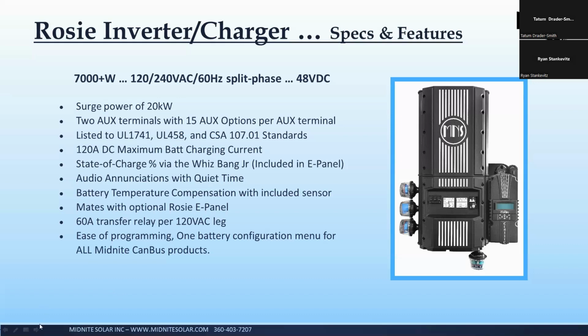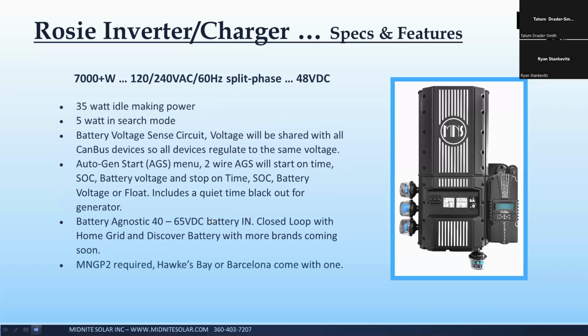And let me see if I can find my arrows. There they are. So some more specifications. 35 watts idle while making power. So, you turn it on, it's making 240 volts out. It's drawing 35 watts. If you put it into search mode, it draws 5 watts. Search mode will behave similar to what you used to, as far as you can set the wattage that you want it to come out of search on, but you're not going to hear that ticking noise like you heard of the old transformer based inverters. And you're not going to see the flicker, like if you had a little bulb on there, you'd see that flicker until the inverter came on. It does it a little differently, but it's the same function. If you set it for 20 watts, when the load hits 20 watts, the inverter turns on.